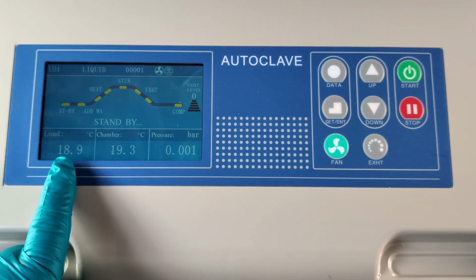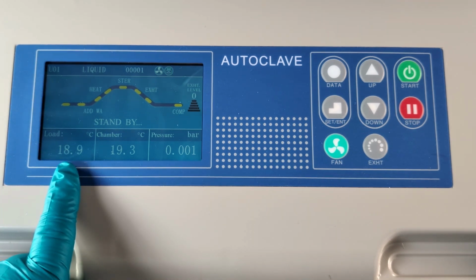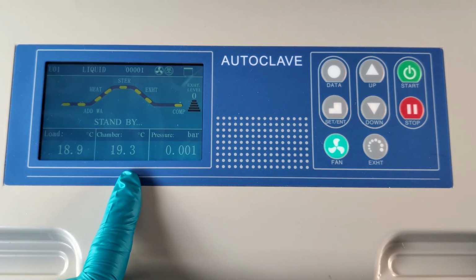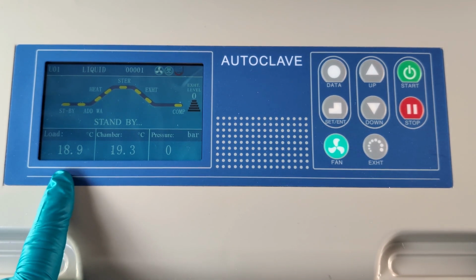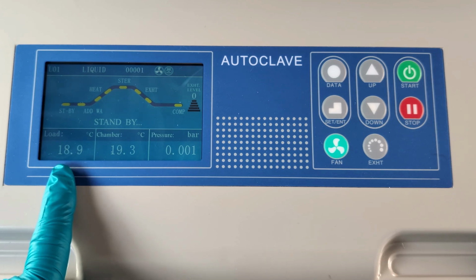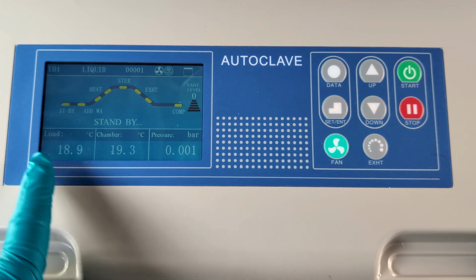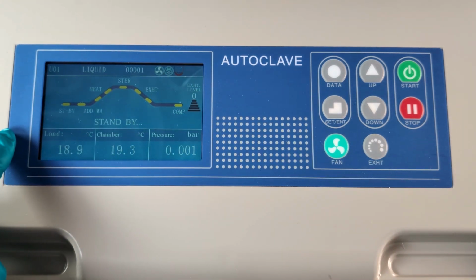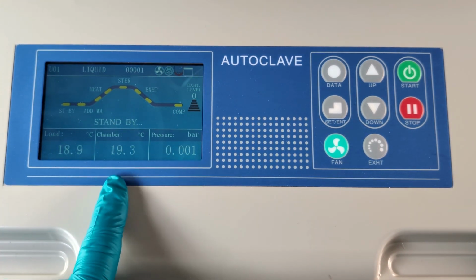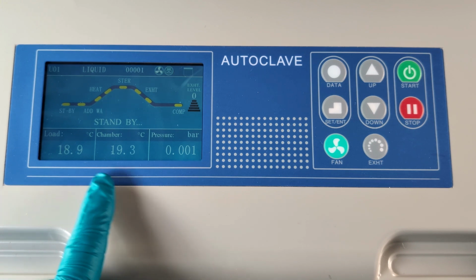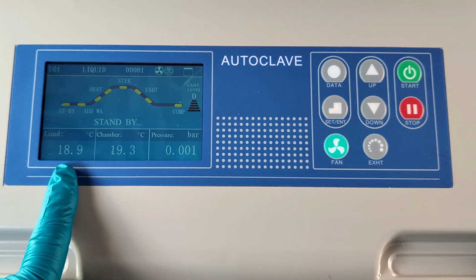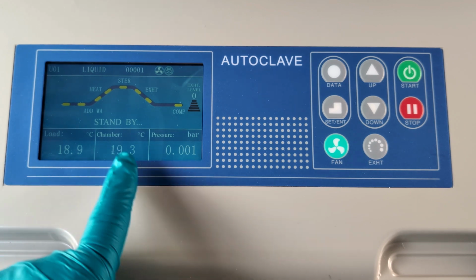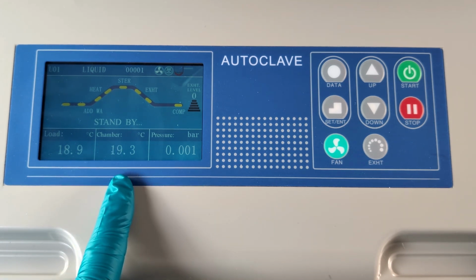To the left, you see the load temperature. Now, the load temperature usually lags behind the autoclave temperature because it takes a while for the load to warm up. And if the load sense probe is turned on, by the way, load sense probes are again standard on this autoclave, then the whole cycle depends on the temperature of the load, not just of the chamber. And it's only when the load gets down to a safe temperature that you are able to open the lid. It doesn't look at the chamber temperature.